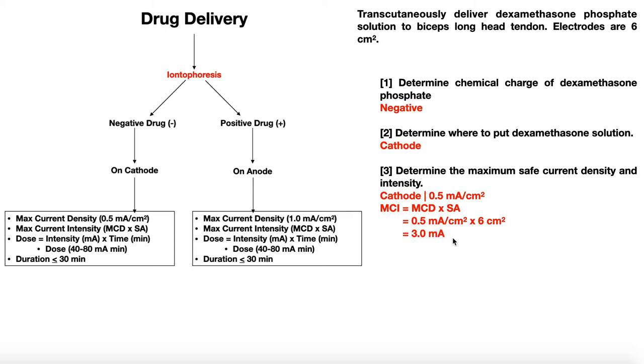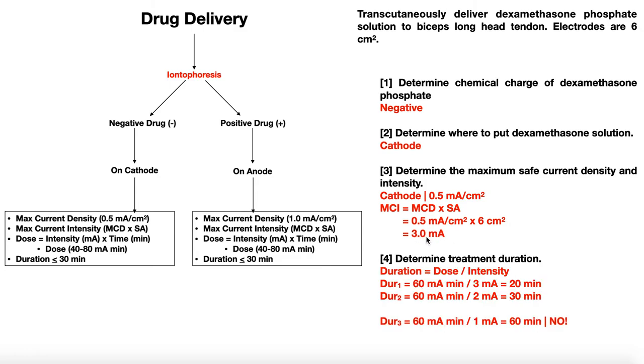Given the maximum safe current intensity is 3 mA, I can use 3 mA or 2 mA, but not 4 mA. For the treatment duration: dose divided by intensity. Using a dose of 60 milliamp-minutes (middle of the 40–80 range) at 3 mA gives 20 minutes. Is this valid? Yes — 3 mA does not exceed the maximum, and 20 minutes is within the 30-minute limit.